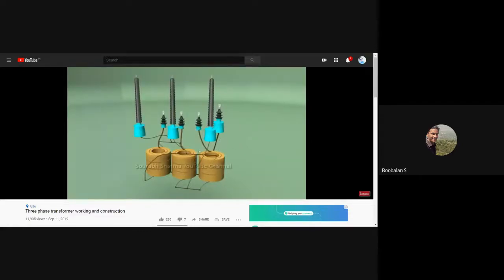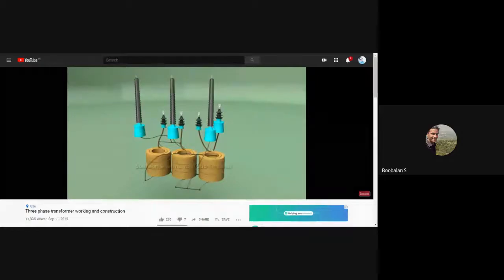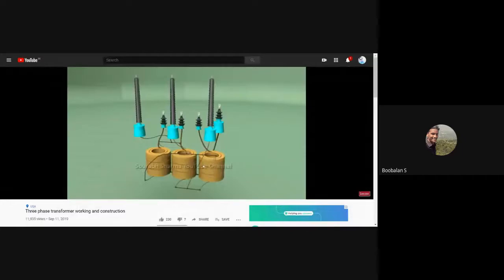The bushing of the low voltage side is of small size, whereas the bushing of the high voltage side is of big size. So this is a type of star-delta transformer, that is, it has a star connection at the low voltage side and a delta connection at the high voltage side. This way the core remains fixed inside the coil and it is held tightly by a holding frame which is bolted over it. To maintain the output voltage of the transformer, a tap changer is used, which is shown here.